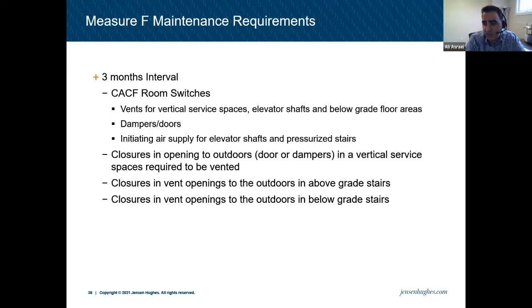Again, from the CACF room, we make sure dampers and doors can be opened and closed, and we can initiate air supply for the elevator shaft and pressurized stairs. Closures to outdoors, these are common. We have to make sure of closures and vent openings to outdoors. Again, for above grade stairs, these are the doors at the bottom. And closure and vent opening to the outdoors and below grade stair. For below grade stair, it could be the door to outside, but that vent is basically more than what the building code is asking. It's okay as long as it's not affecting the performance of the system.